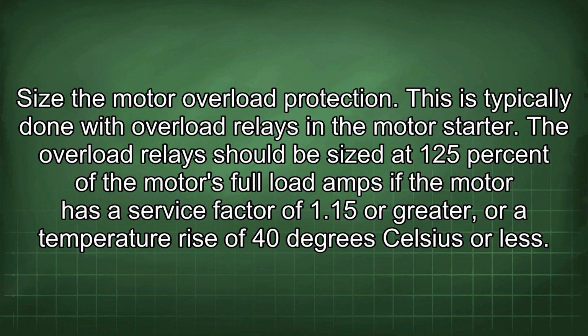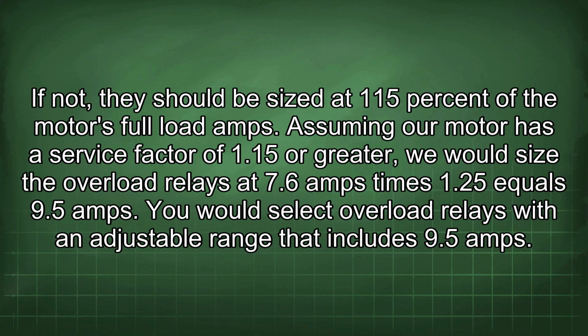Size the motor overload protection. This is typically done with overload relays in the motor starter. The overload relays should be sized at 125% of the motor's full load amps if the motor has a service factor of 1.15 or greater, or a temperature rise of 40 degrees Celsius or less. If not, they should be sized at 115% of the motor's full load amps. Assuming our motor has a service factor of 1.15 or greater, we would size the overload relays at 7.6 amps times 1.25 equals 9.5 amps. You would select overload relays with an adjustable range that includes 9.5 amps.